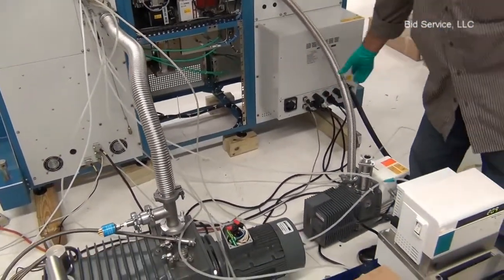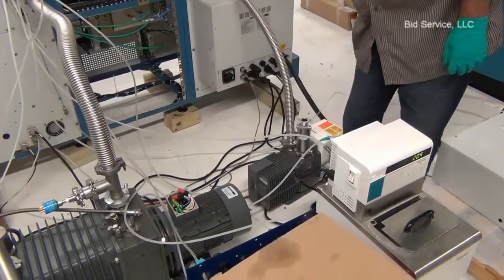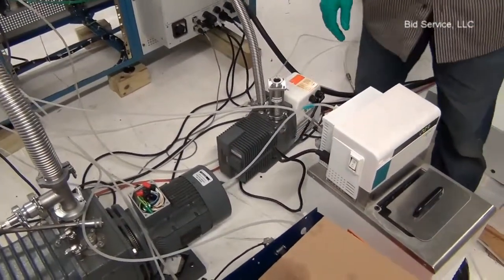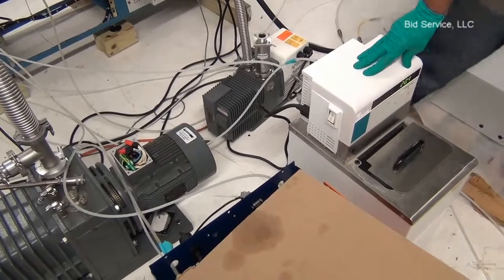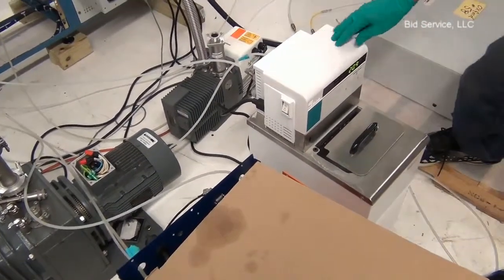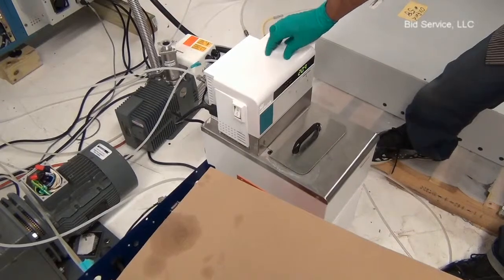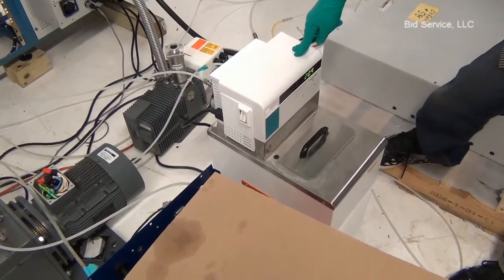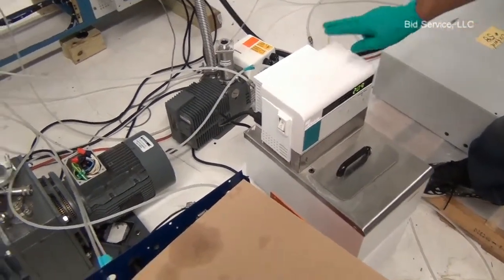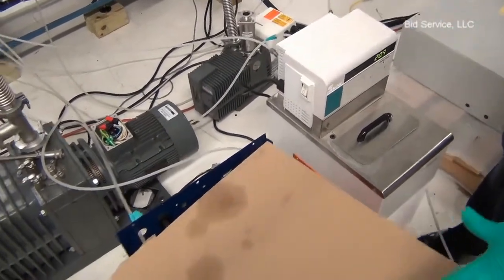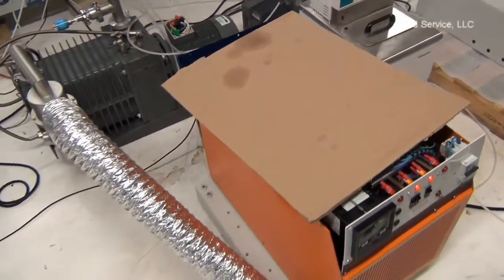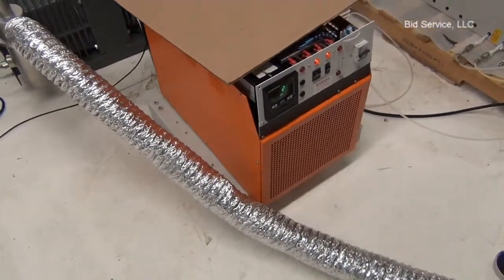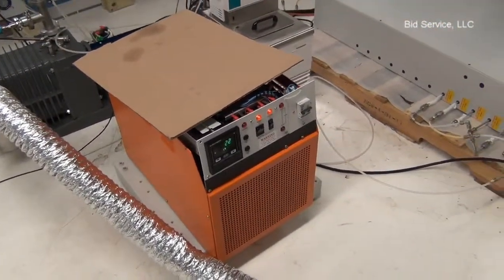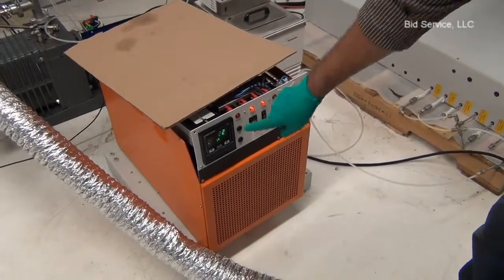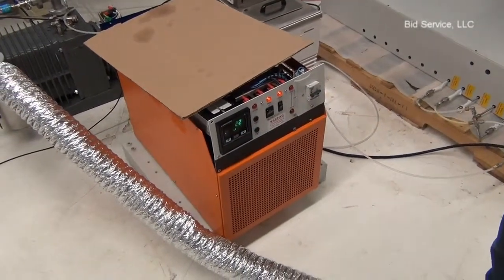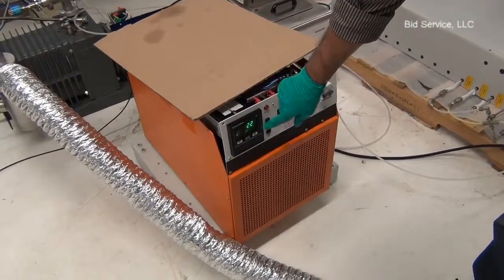The mechanical pump is filled with pump oil. And this is the RTE111 Neslab chiller. I'm using this for cooling both the main turbo molecular pump and the auto matching network. And this is the second chiller. This is for the process temperature control for the bottom electrode. Now the set point is transmitted from the computer to the Eurotherm controller.